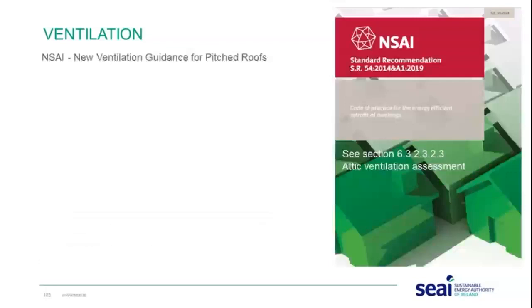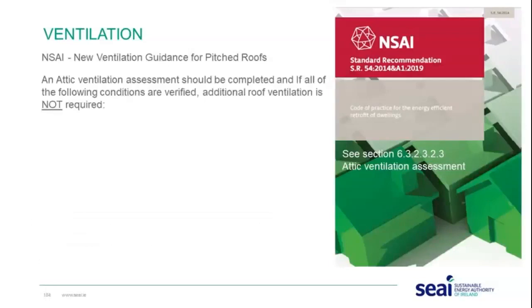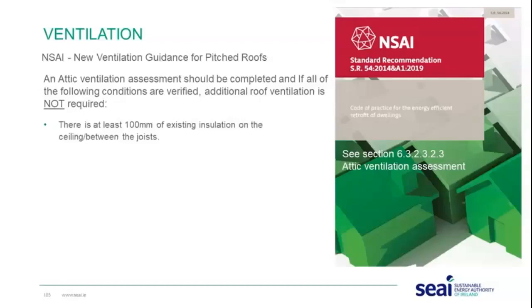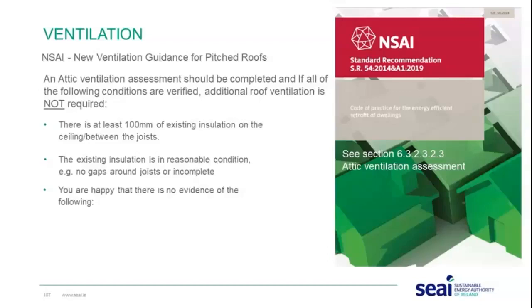SR 54 includes new ventilation guidance for pitched roofs: an attic ventilation assessment should be carried out, and additional roof ventilation is not required if all of the following conditions are met — at least 100 millimetres of existing insulation on the ceiling between the joists, the existing insulation is in good condition with no gaps around joists or incomplete sections, and there is no evidence of mould, moisture, or large droplets of condensation. If all conditions are met, no additional roof ventilation is required as per SR 54:2019.